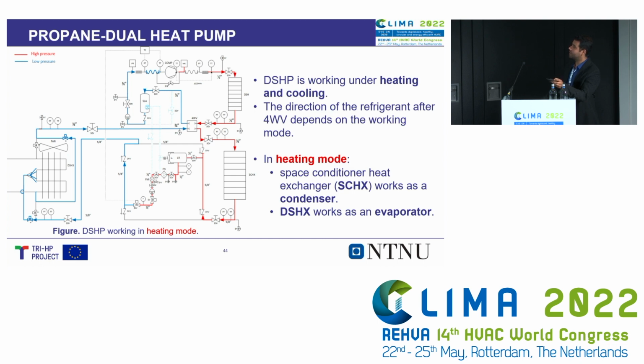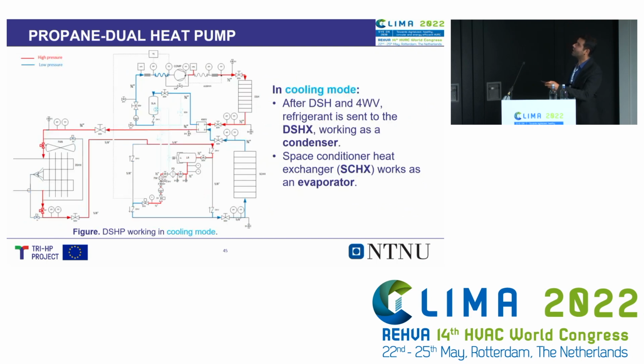So, for example, under the heating mode, the dual source heat exchanger works as the evaporator, and our space conditioner heat exchanger works as the condenser. So the refrigerant after the four-way valve is sent to the space conditioner heat exchanger, passes through the evaporator, which is the dual source heat exchanger, and then goes to the suction of the compressor, and then we have the cycle. In this slide, we have the propane dual source system, but this time working in the cooling mode. After the four-way valve, the refrigerant is sent to the dual source heat exchanger, which works as a condenser this time, and our space conditioner heat exchanger works as the evaporator. In this way, the system is able to work in both heating and cooling.